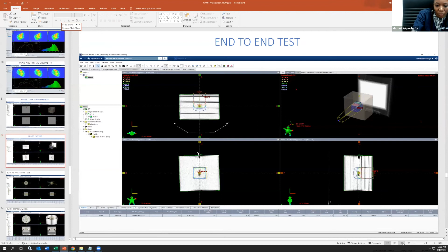Okay, so after the point dose measurement, another verification test we carried out was the end-to-end test. How did we do it? The end-to-end test is like mimicking a proper treatment from start to end. Using the phantom, an ionization chamber is placed within the phantom and simulated. The images are acquired and planned on, and we calculate the dose. Then this phantom with the ionization chamber is taken for treatment. The dose measured by the ionization chamber during treatment is compared with that from the treatment planning system, and it was comparable.